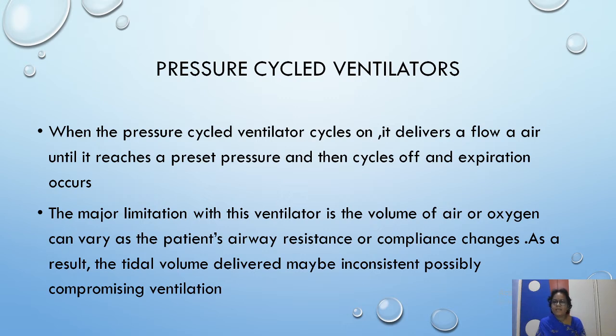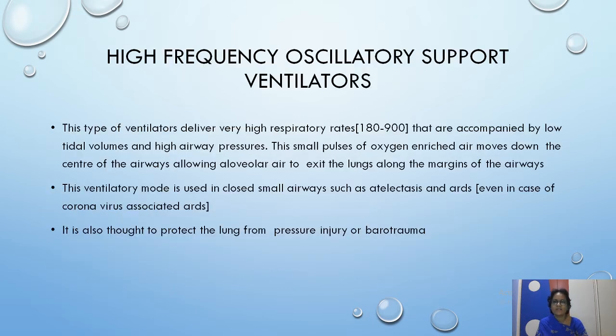The major limitation with this ventilator is that the volume of air or oxygen can vary as the patient's airway resistance or compliance changes. As a result, the tidal volume delivered may be inconsistent, possibly compromising the ventilation. This is the only limitation or disadvantage.